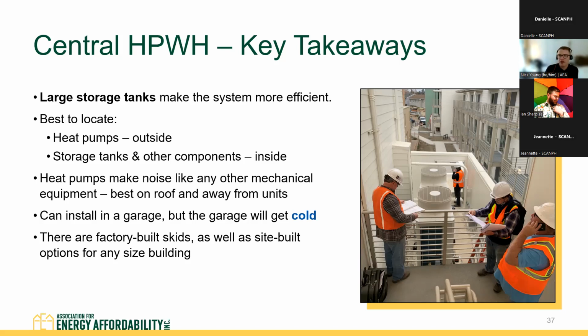If this is about a residential heat pump water heater, which it probably is since the question was asked about 10 minutes ago, you could put a residential size heat pump water heater in a garage without a closet, no problem. The problem with those units arises when you put them in a very small space with little to no ventilation. And the answer is not to put in a fan, because that's just more energy used to correct the problem we created by putting it in the wrong kind of location. I've seen over-engineered solutions where we put a heat pump in the wrong place and then add more fans because of that. We should just put the heat pump in the right place, which is a place that has ventilation.